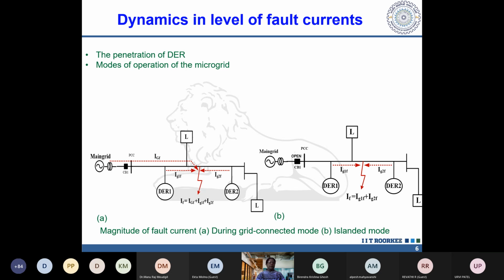This is due to the integration of renewables. Here they are named DER, distributed energy resources, which is the IEEE standard name; sometimes we call them DGs, distributed generators. Here two renewables are connected, DER1 and DER2, and these are the loads, load 1 and load 2, and this is the main grid. When a fault is created in this feeder, which originates from the main grid through this PCC, one current comes from the main grid side, that is IGF, and these two are the fault currents contributed by DER1 and DER2, IGF1 and IGF2. So the total fault current is the sum of the fault current contributed by the grid and by all the renewable sources present in the microgrid.